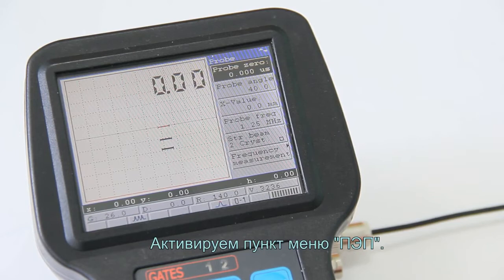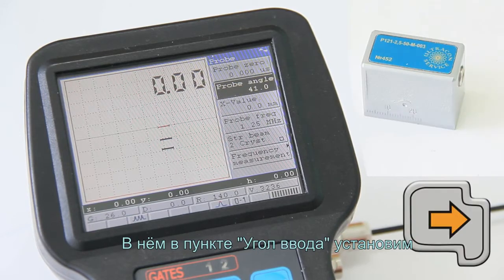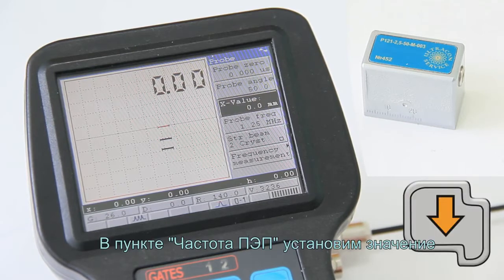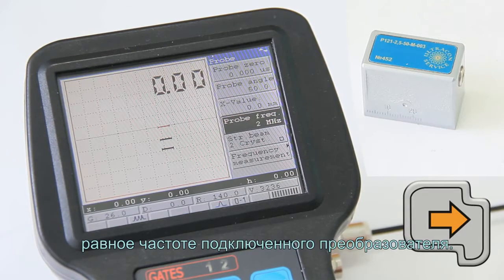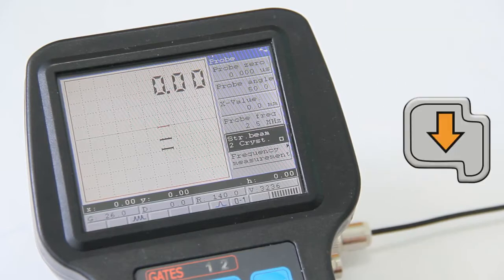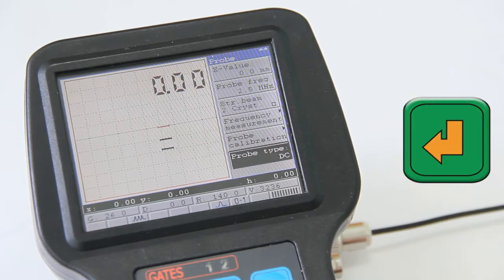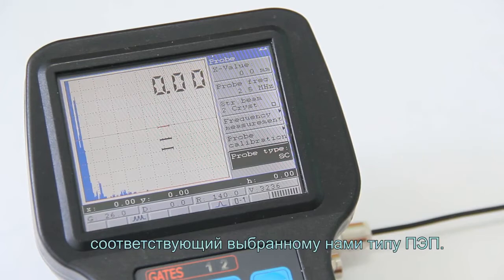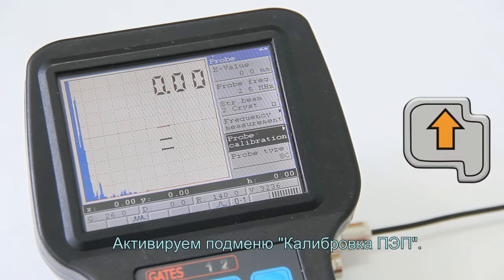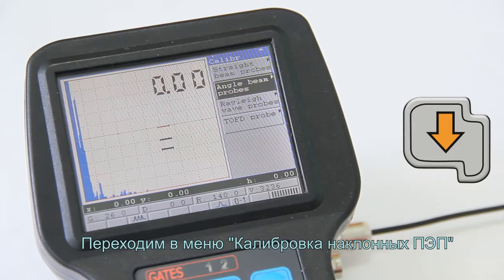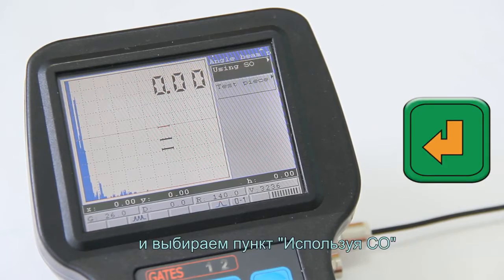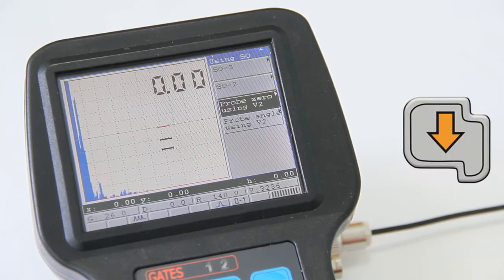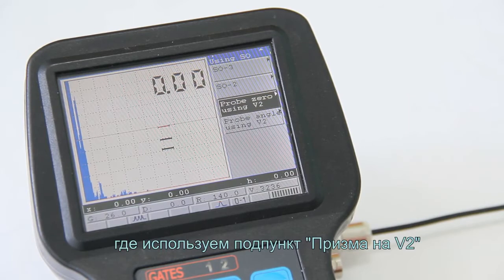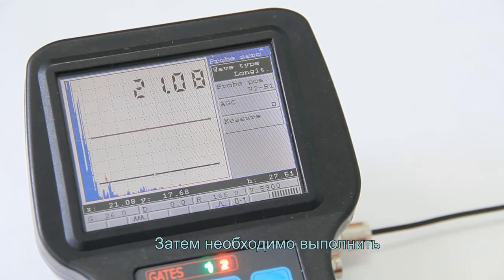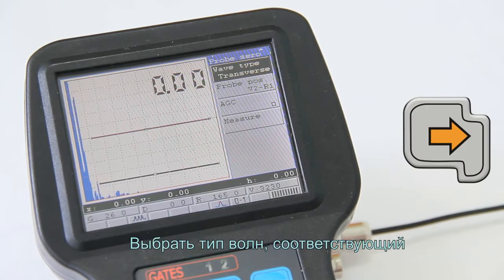Activate the Probe menu item. Here, in Probe Angle item, set the required value for the probe angle. In Probe Frequency item, set the value that equals the frequency of a connected probe. In Probe Type item, set the variant that corresponds to the probe type that we have selected for testing. Activate the sub-menu Probe Calibration, then move to the menu Angle Beam Probes Calibration and select item using SO, it is calibration block, where we use the sub-menu Probe zero using V2. Then you should do the following actions.